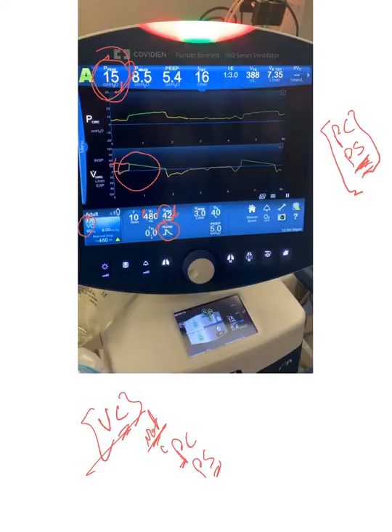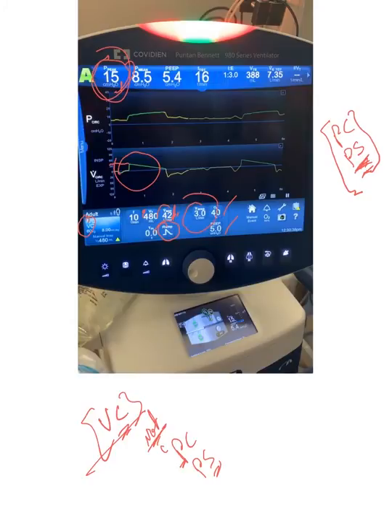And of course, fix any underlying problem that could lead to this. I just want to show you where to locate on this kind of ventilator the peak inspiratory pressure. Again, quickly: this is the FiO2, this is the PEEP, and this is the flow trigger.